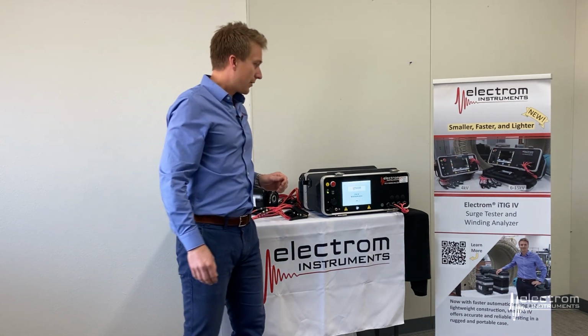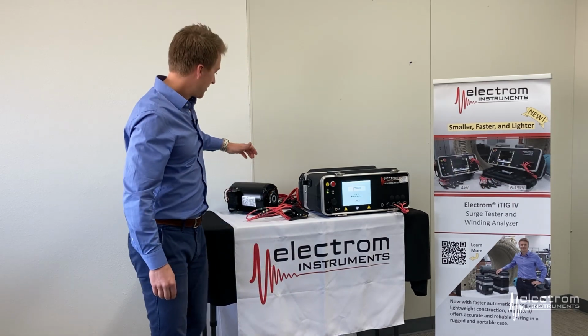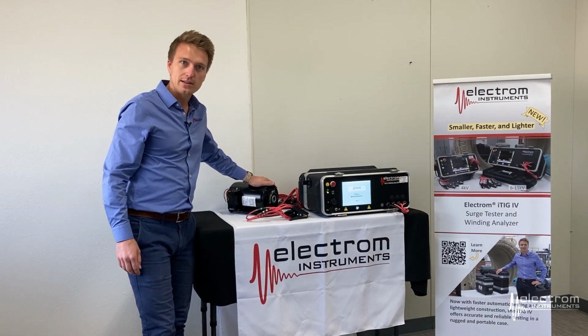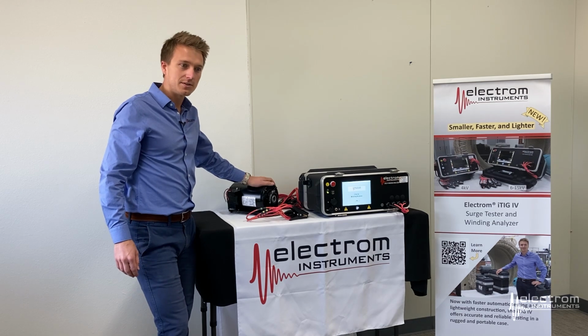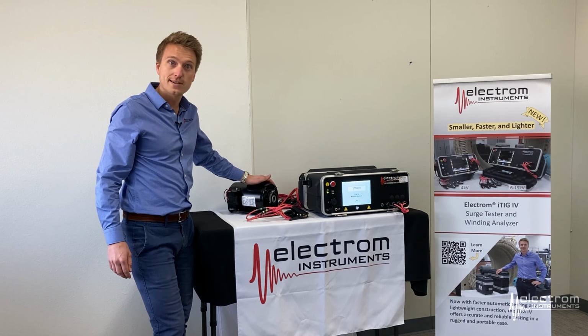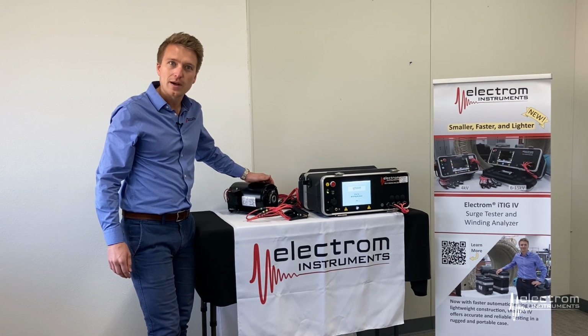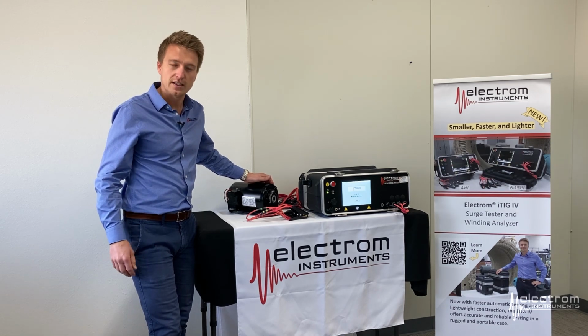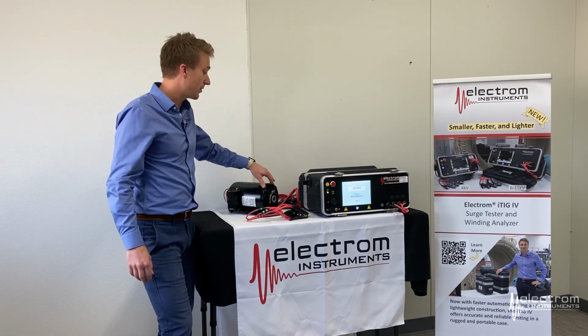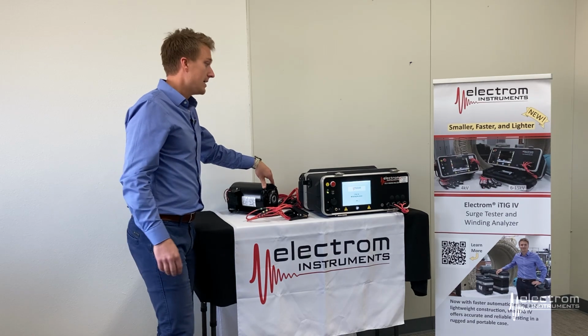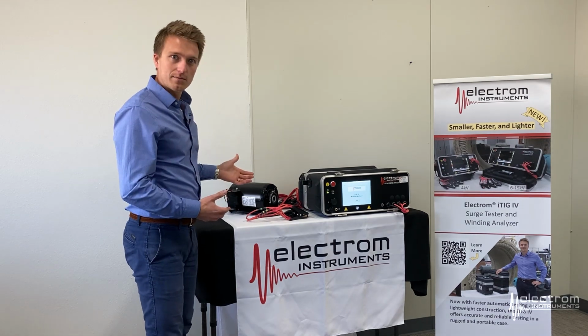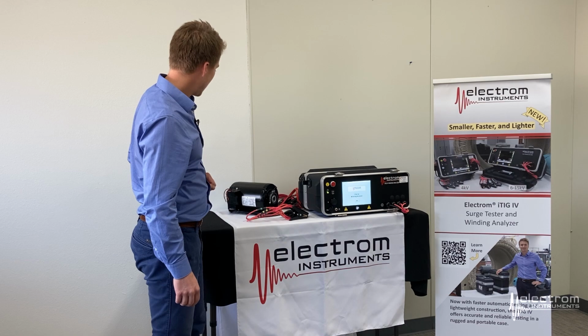We are going to do a quick demonstration on this 460 volt concentric wound stator. We will see some interesting results in the surge test. Because this is concentric wound, it will have some inherent differences in the 3 phases, so the surge waves will not match. But we know that going into it, so we will test it nonetheless and see what we can find.